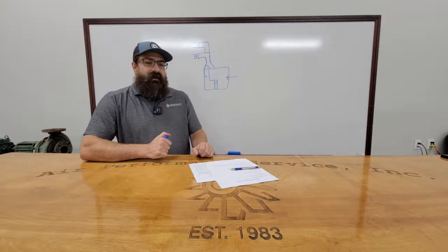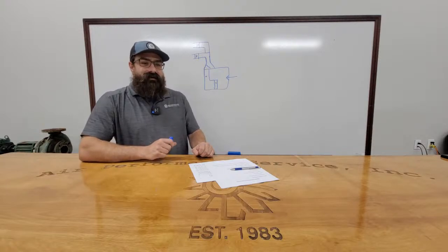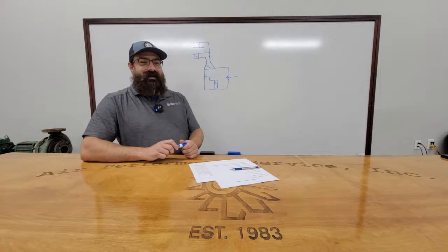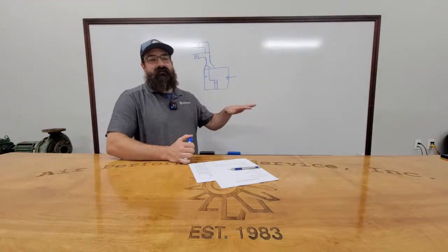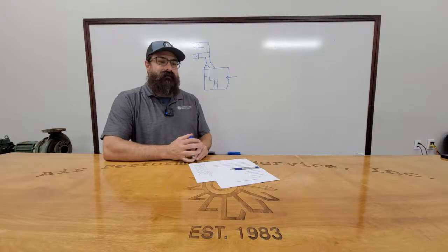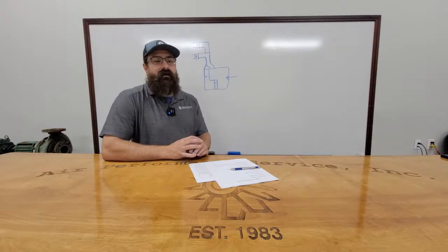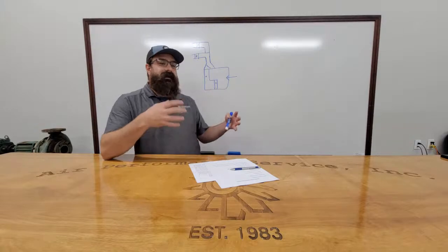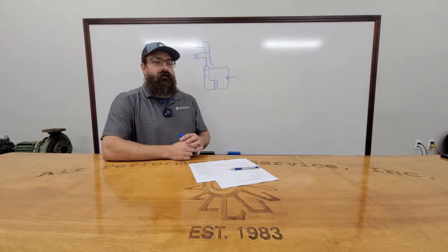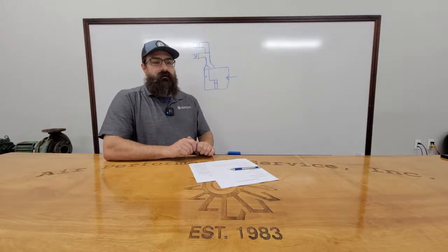But a lot of stuff we have in Austin is not passive outside air. It is active outside air. So it's got like a makeup air machine with cooling on it, and it's supplying 70 degree air all the time. Tempering. Yeah, tempering it. It doesn't need to be cold, but you bring in like 70, 75. That way it's meeting return temp. They call that like neutral or something.